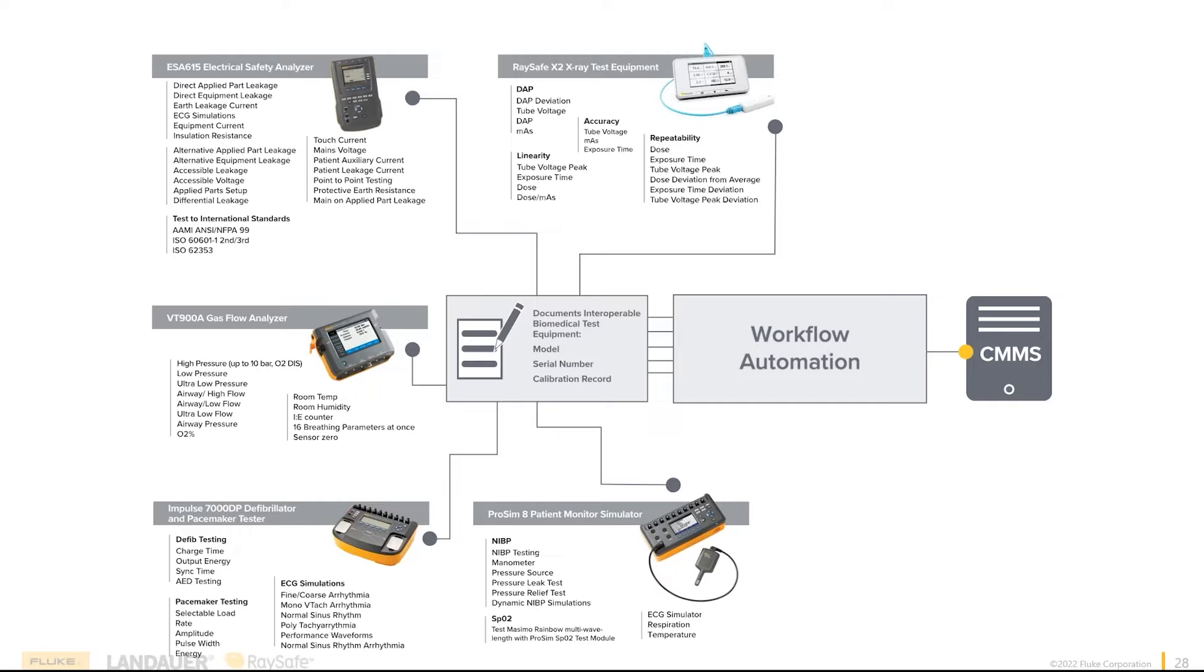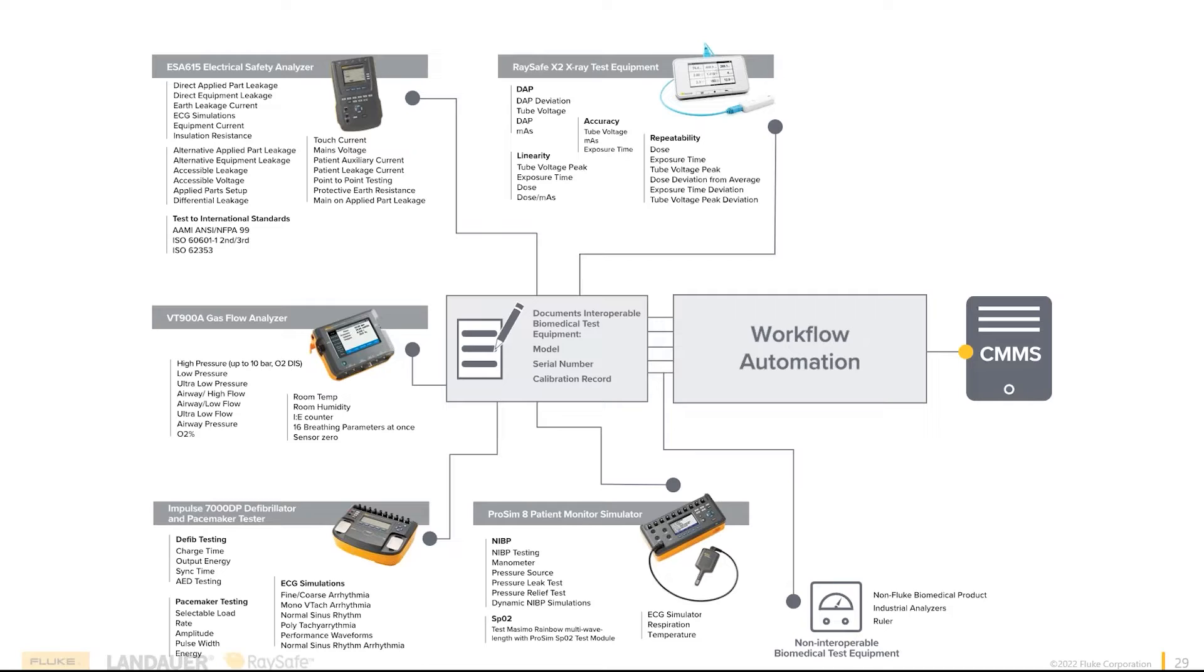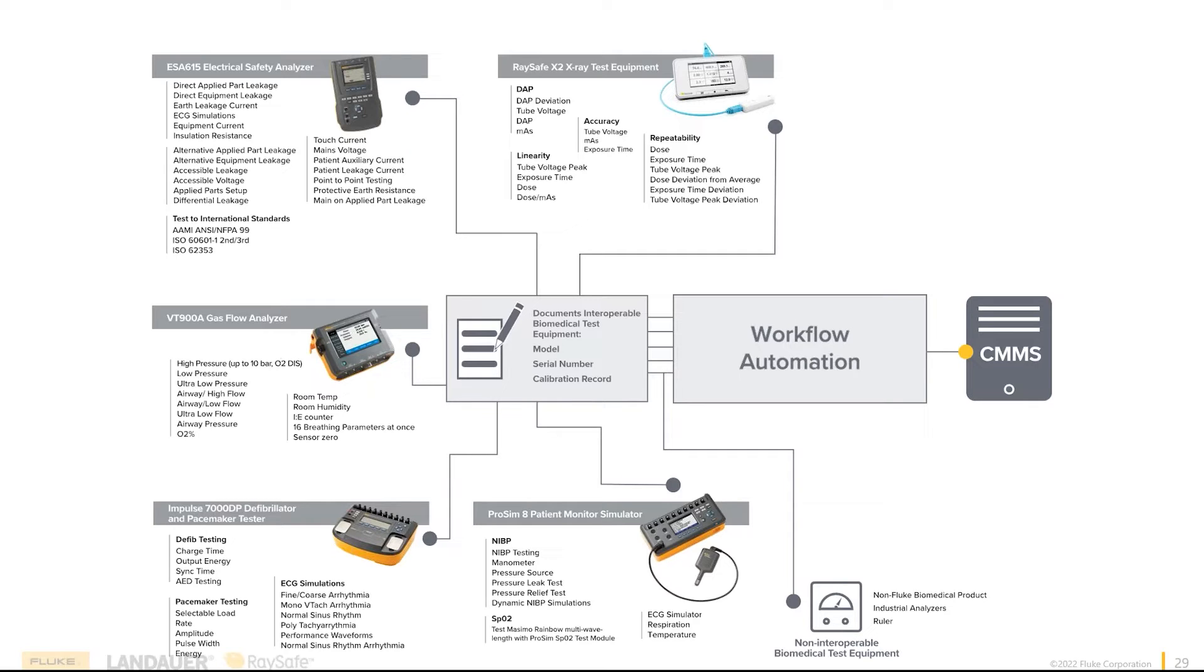But it's more than just the interoperable devices. How about the non-interoperable devices, the old legacy devices, or maybe you have a blood gas analyzer? Not a big deal. We can simply build a test procedure that will give you a yes-no answer or have a data input entry. Maybe it's a numerical entry and you can put a tolerance in it. If the answer has to be five and you have a tolerance of 0.5, you type in 5.3. If it's passing in that tolerance, it moves on. You still get so much of this even with non-interoperable devices. It also works with something as simplistic as a ruler. You can use a ruler and still get the benefits of 1QA.